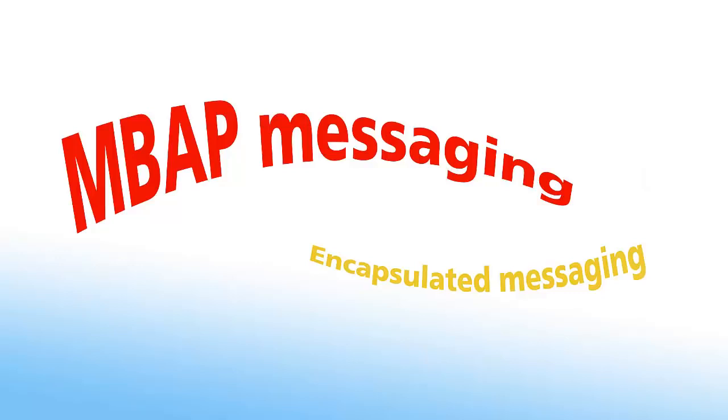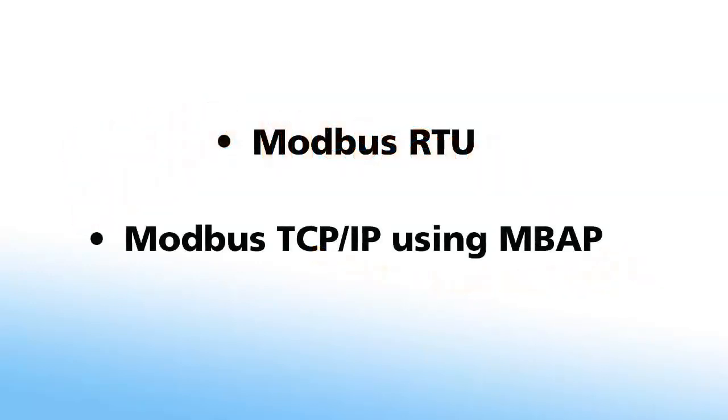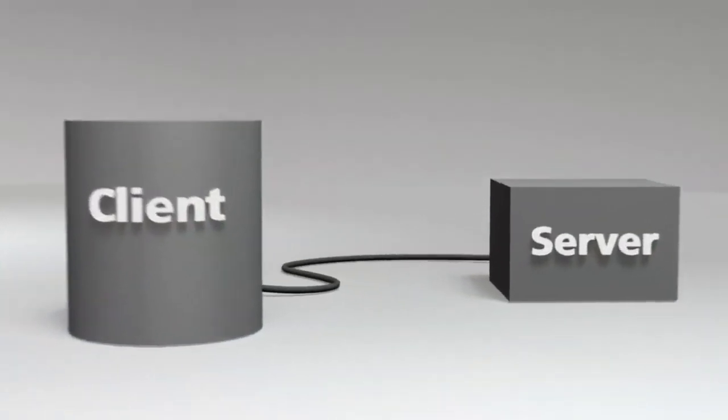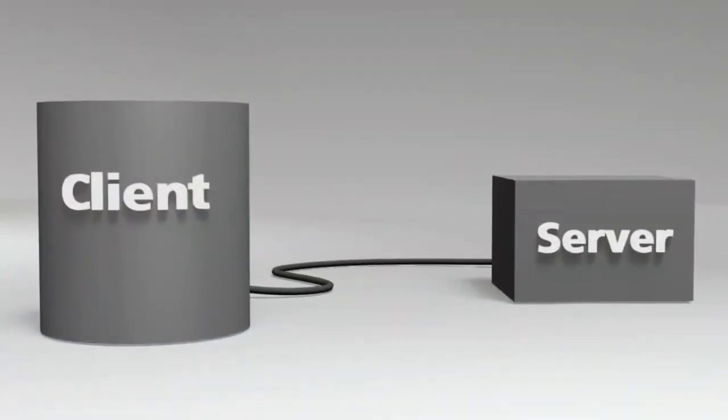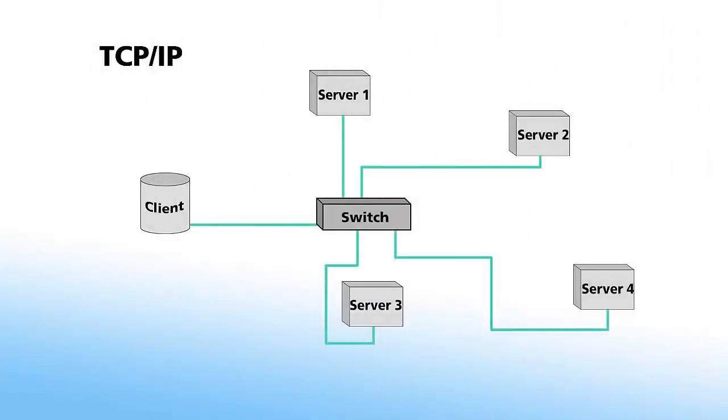MBAP messaging is by far the most popular Modbus TCP/IP communication method, so for this video we'll be focusing on Modbus RTU and Modbus TCP/IP using MBAP. Modbus TCP/IP uses the terms client and server instead of master and slave. The TCP/IP network consists of the client connected to a switch or a series of switches to which all the servers on the network are also connected.